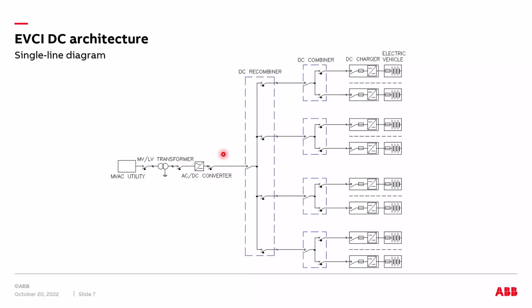We will see later on the internal architecture of this AC-DC converter. Usually, this AC-DC converter has to be bidirectional in order to allow the battery charging, but also the so-called electric vehicle to grid function. So in order to be able to inject, in some cases, the power also into the AC grid, this AC-DC converter can be bidirectional. And then we have the connection with the medium voltage AC utility by means of a typical and common medium voltage low voltage transformer.